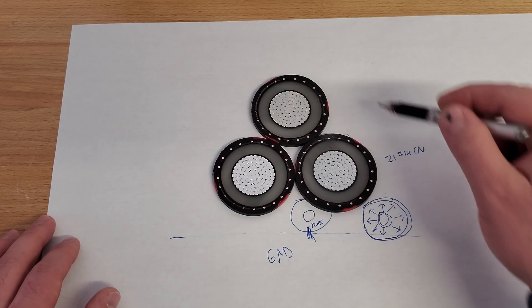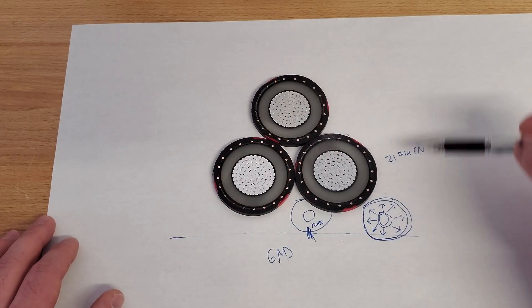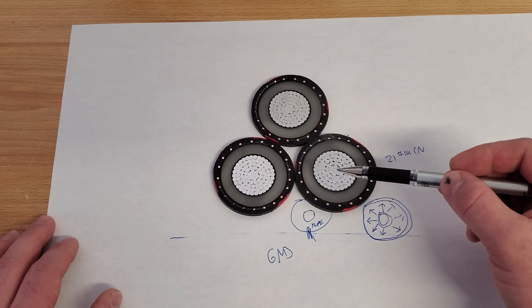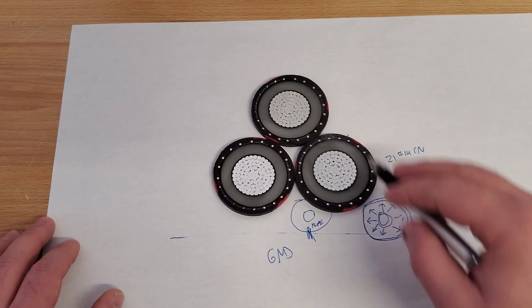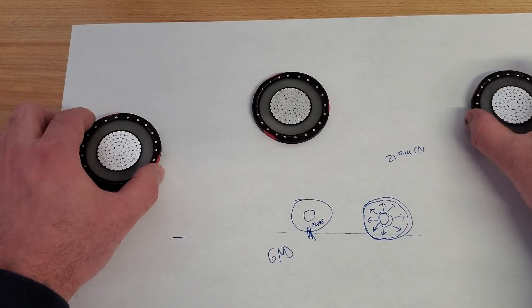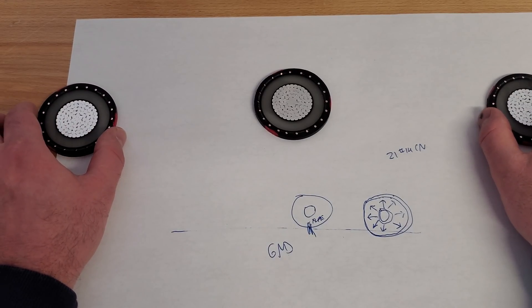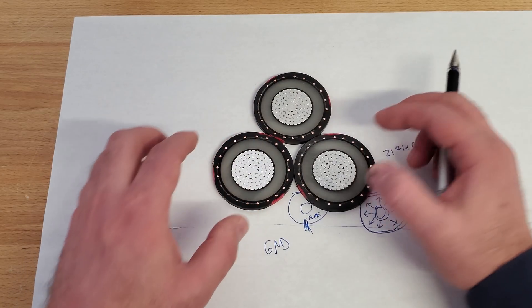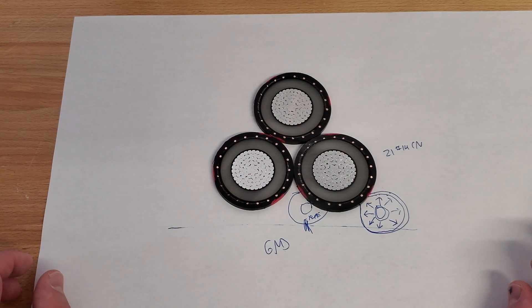It's almost all our wind farms we do this way. And what that does is cancels out the electromagnetic field, the EMF with these cables, and it keeps the heating down. So believe it or not, you'll have less heating like this than you will if these are separated a lot further out, it cancels out that EMF field. So anyway, that in a nutshell is the 35kV cable.